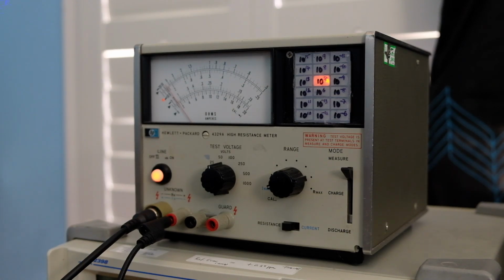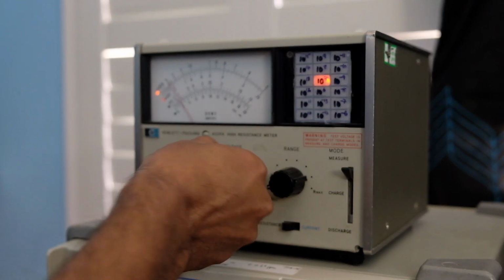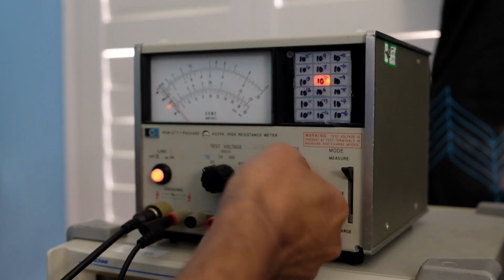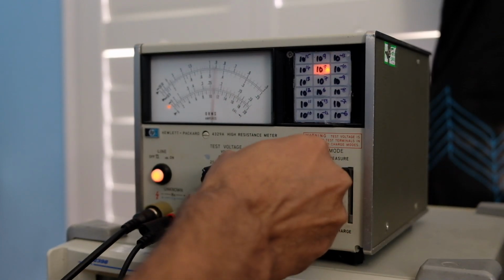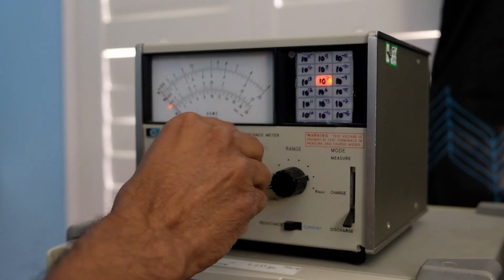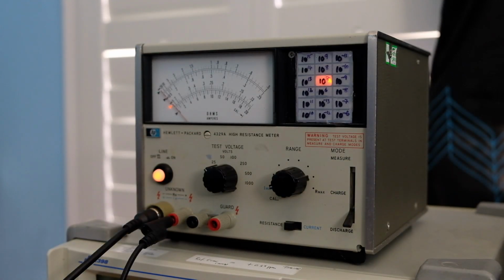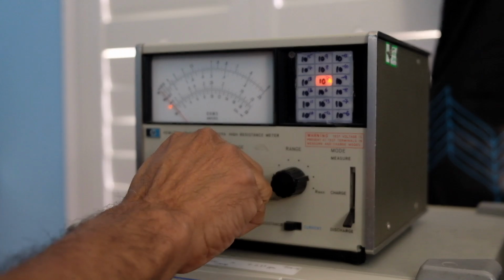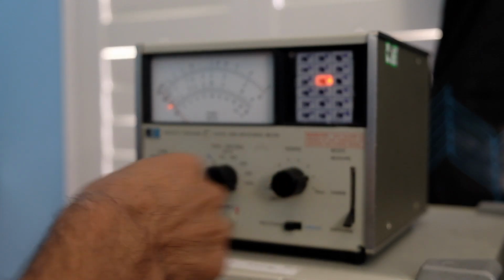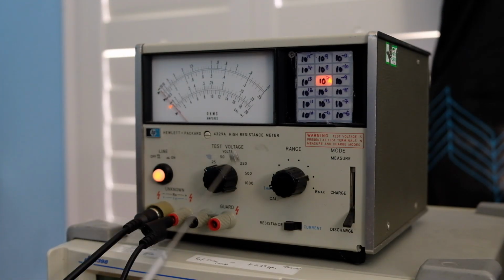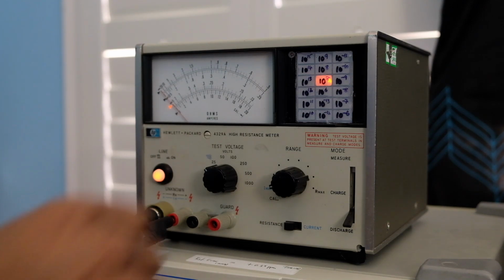I forgot to mention one thing. When I got it, it was basically working, but when I was switching through the different test voltage ranges as well as the actual range, I was getting a lot of noise, and the output didn't make sense. In fact, it wasn't even working properly. So I cleaned all the internal contacts on the switches for both of them, and that brought it back to life.